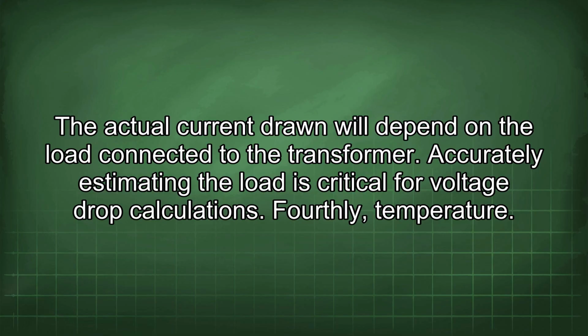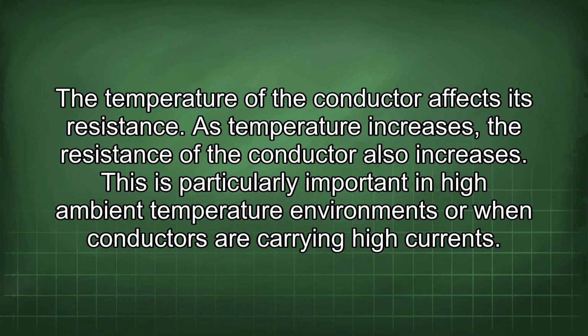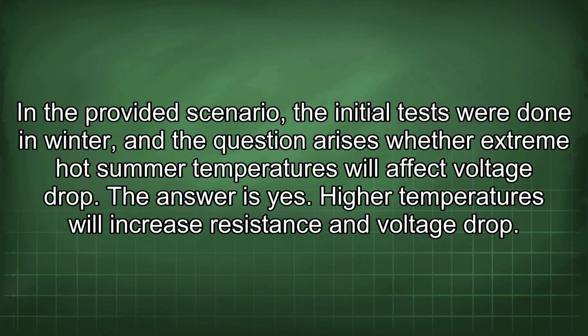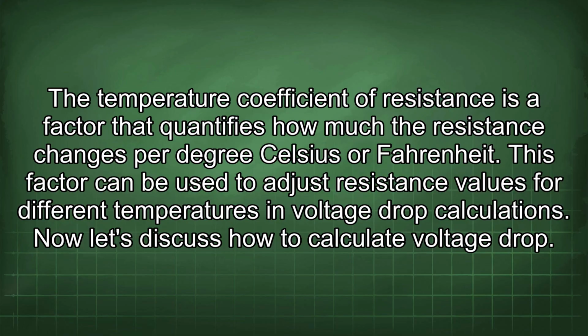Fourthly, temperature. The temperature of the conductor affects its resistance. As temperature increases, the resistance of the conductor also increases. This is particularly important in high ambient temperature environments or when conductors are carrying high currents. In the provided scenario, the initial tests were done in winter, and the question arises whether extreme hot summer temperatures will affect voltage drop. The answer is yes. Higher temperatures will increase resistance and voltage drop. The temperature coefficient of resistance is a factor that quantifies how much the resistance changes per degree Celsius or Fahrenheit. This factor can be used to adjust resistance values for different temperatures in voltage drop calculations.